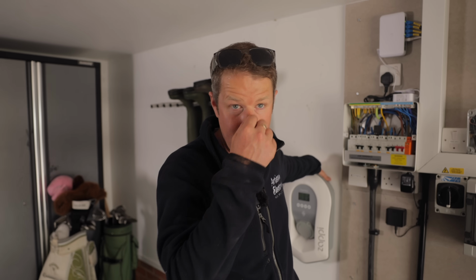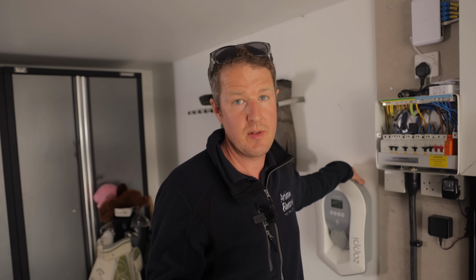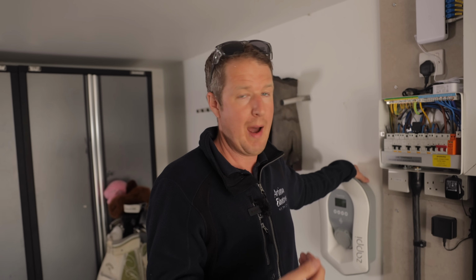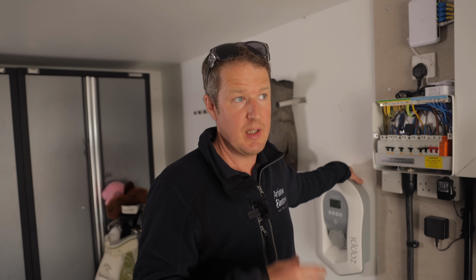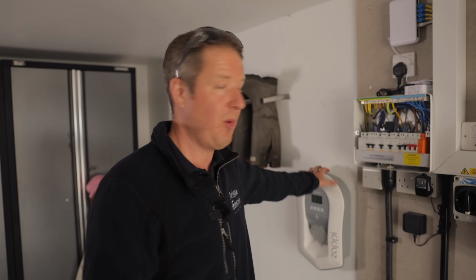Another thing you need to do when installing a Libbi is set a grid limit to protect the main fuse. That's all about import, so how much power you're pulling into the property. You don't want all of the MyEnergi devices to be pulling power at the same time, as well as running loads of stuff in the house and blow the main fuse. So like here, for example, the Zappi could be pulling 7 kilowatts, the Libbi could be pulling 5. That's already 12 kilowatts. Plus maybe they're running a heat pump and an electric shower and stuff in the house. Suddenly 100 amp main fuse goes pop.